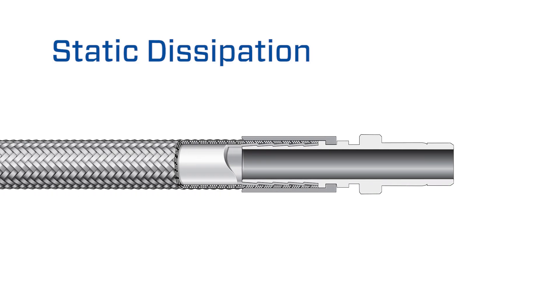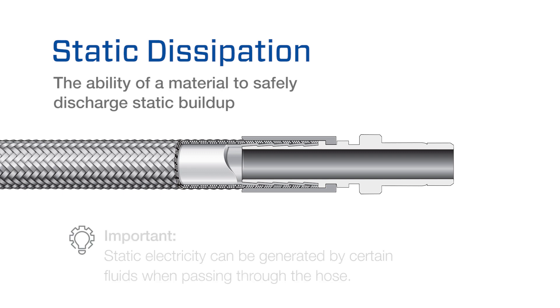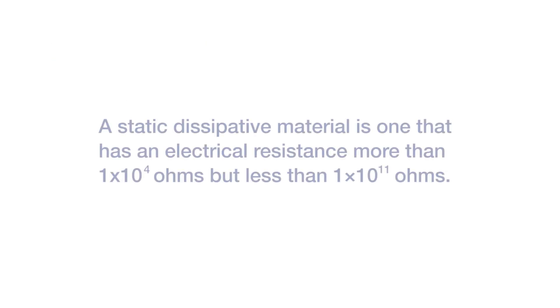Static dissipation is the ability of a material to safely discharge static buildup. This is important because static electricity can be generated by certain fluids when passing through the hose. A common definition of a material that is static dissipative is one that has an electrical resistance more than 1×10⁴ ohms but less than 1×10¹¹ ohms.